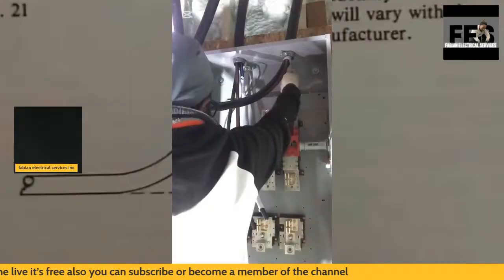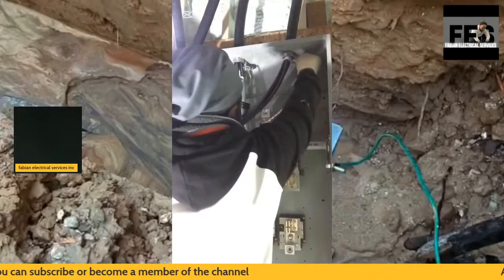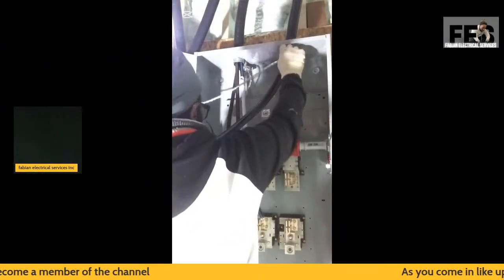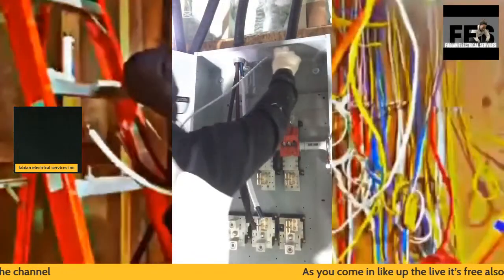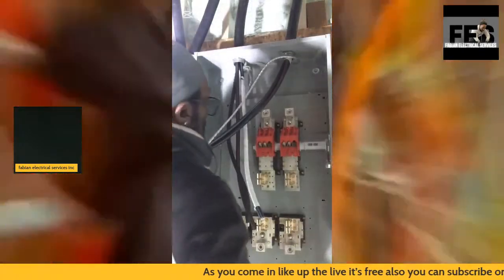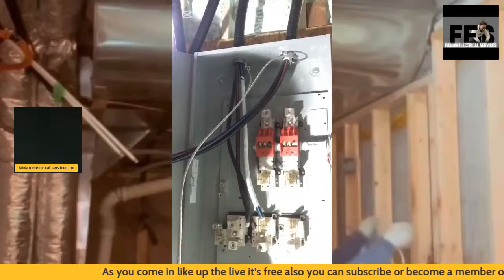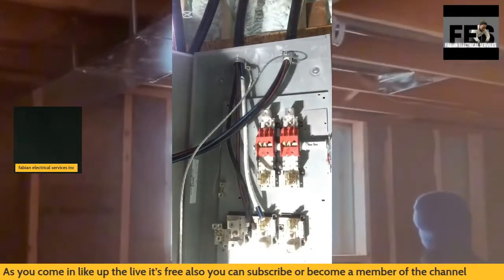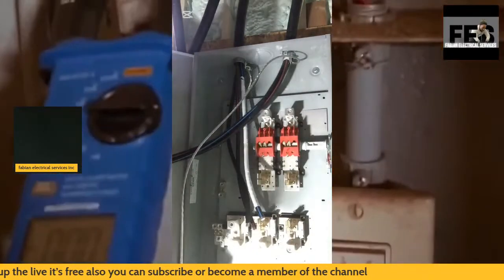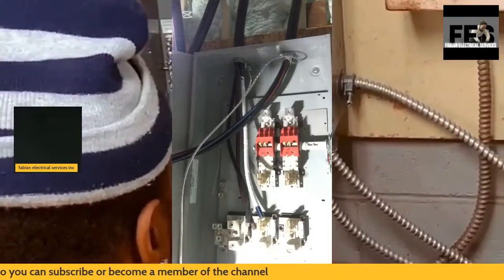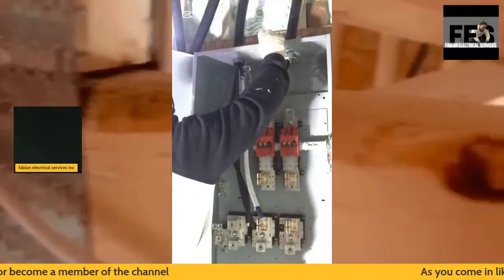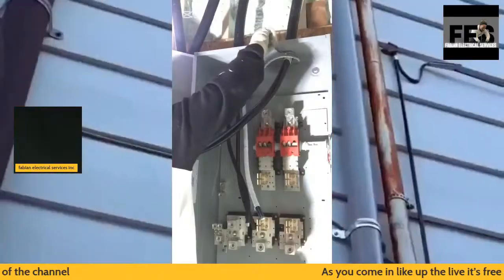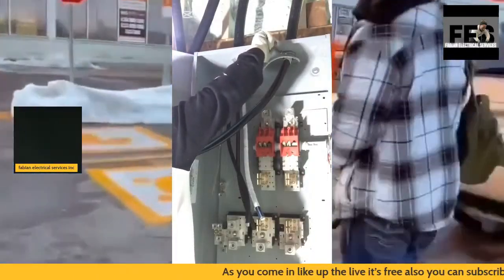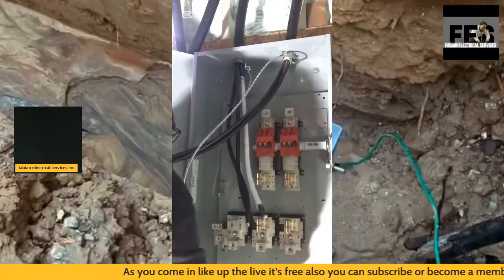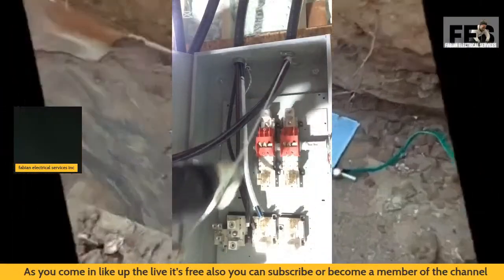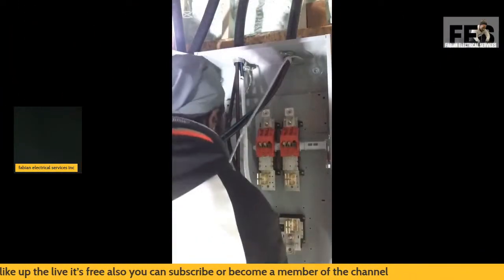So as you can see, the reason why I said I like to keep the white paper on is it simply helps with the cable. As you can see, the cable is locked in place. Once you disassemble that, it gives you a lot more problems to get the cable inside of the connector. So that's why I always make sure I land my cables inside of the disconnect, inside of the connectors, and then I make sure that I remove that.